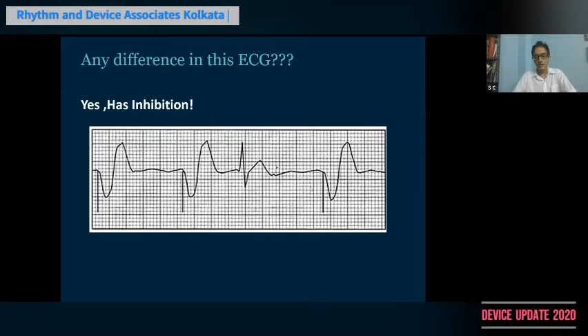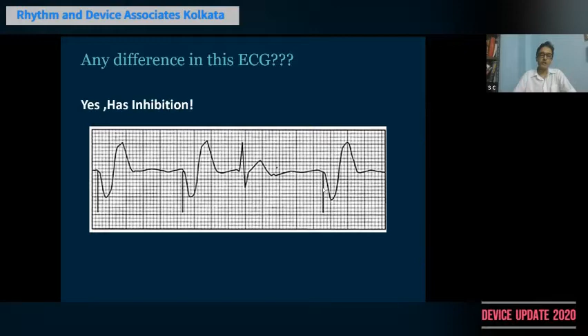So what is different in this ECG? The difference is the third complex, which is an intrinsic complex. Because of this intrinsic QRS, the pacemaker detects this QRS and stops pacing for a certain period of time. There is no intrinsic activity detected again, and therefore the next pacing spike occurs. This is what is meant by sensing and inhibition due to detection of intrinsic events.